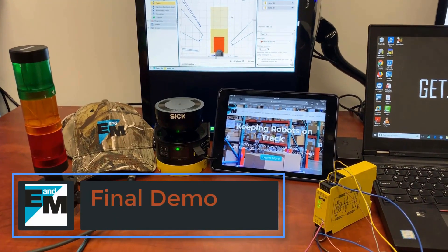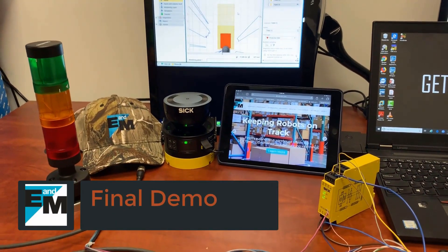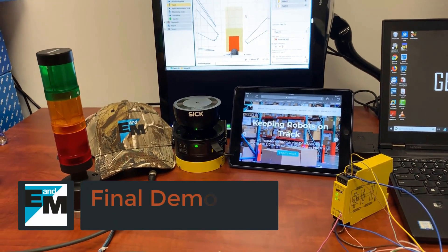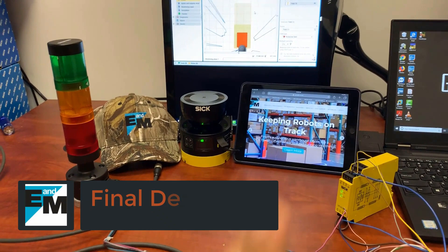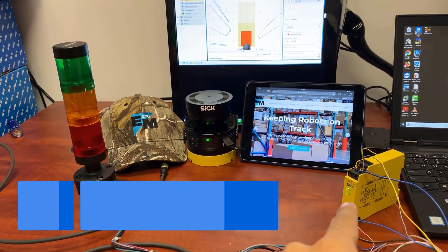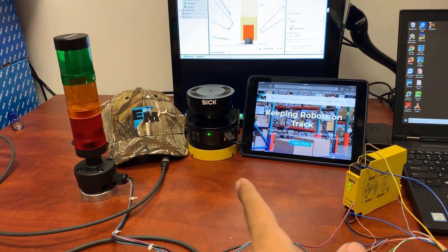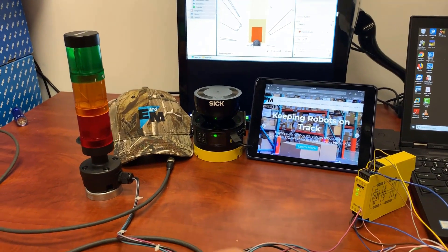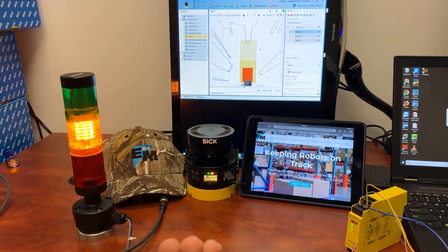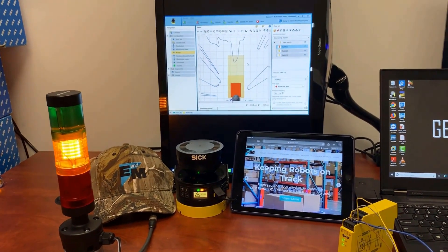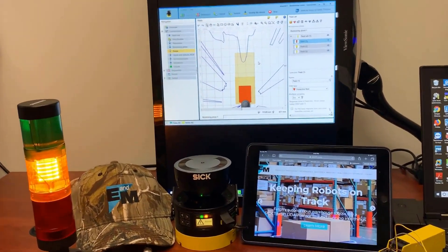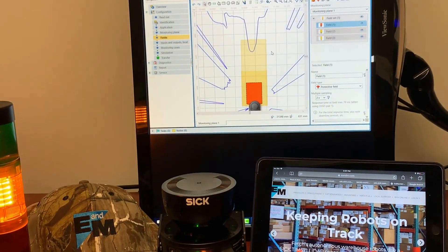Okay, so you can clearly see everything is connected now. We have Microscan's two outputs going to the stack light and one input coming in from the relay and as soon as we breach the first warning zone, we get yellow light. You can even see on the graph right there.